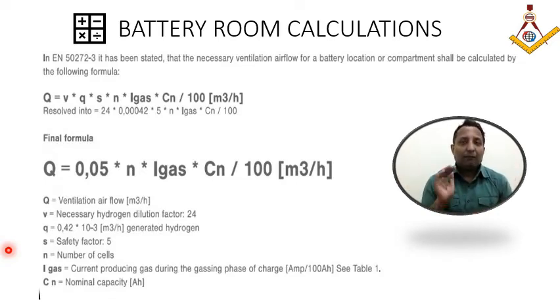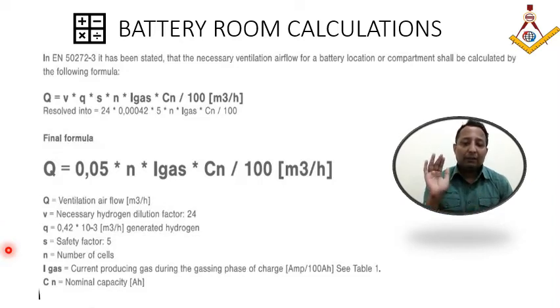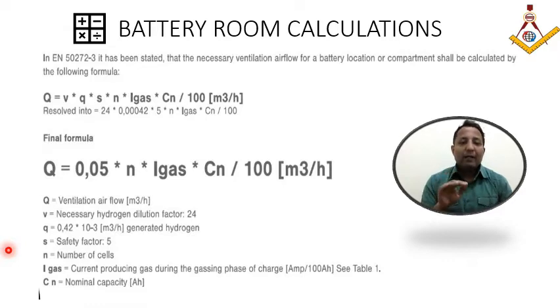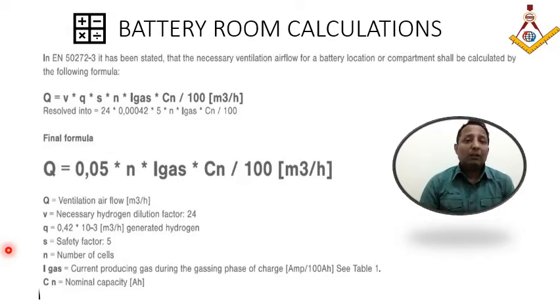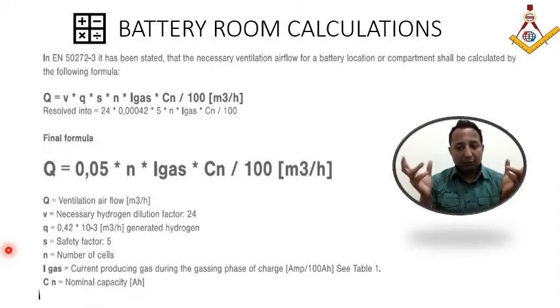When we talk about the requirement of air-conditioned air supplied to the battery room, it is always supplied at the floor level. A draft effect should happen so the gas gets pushed upward toward the ceiling level, so that it gets sucked out properly.